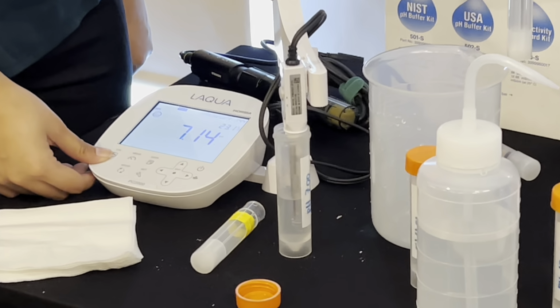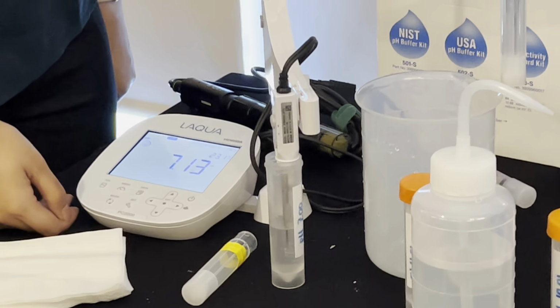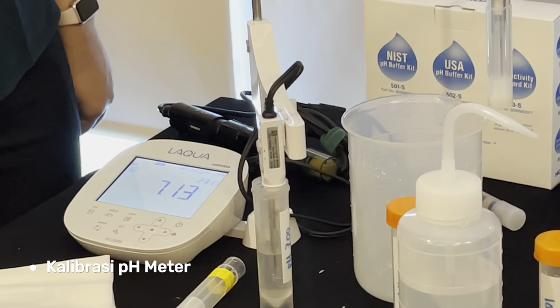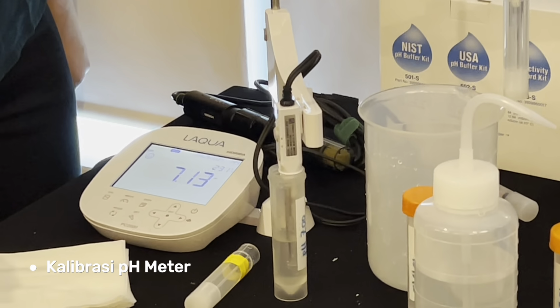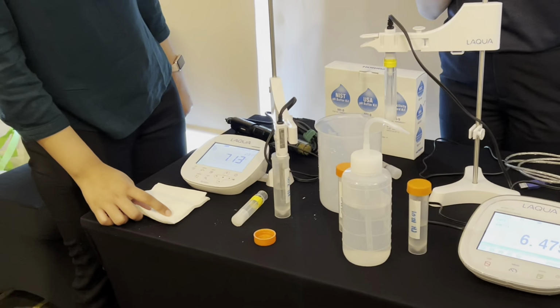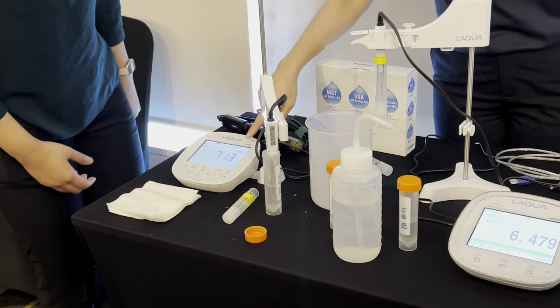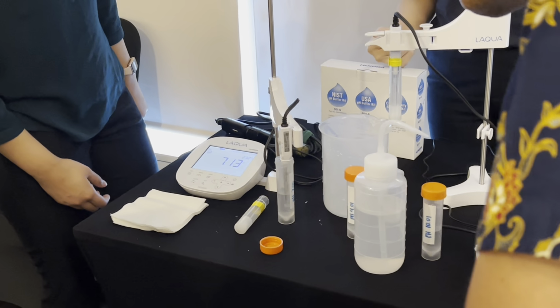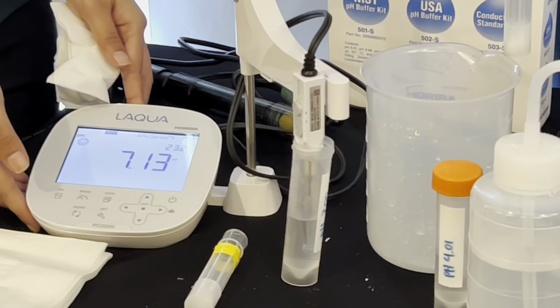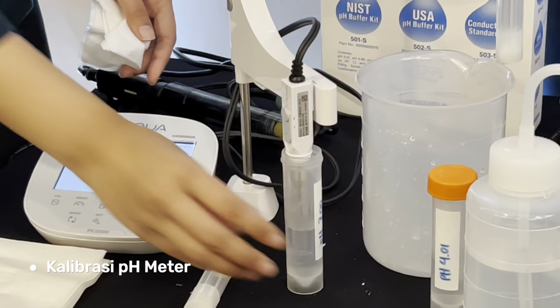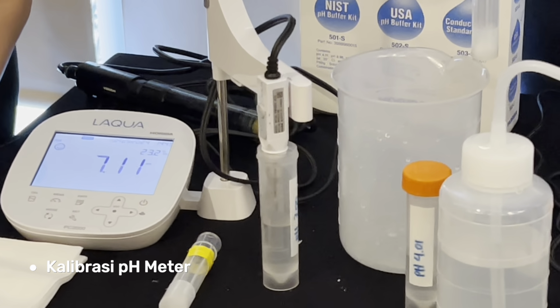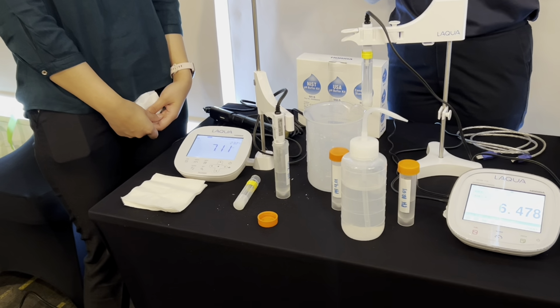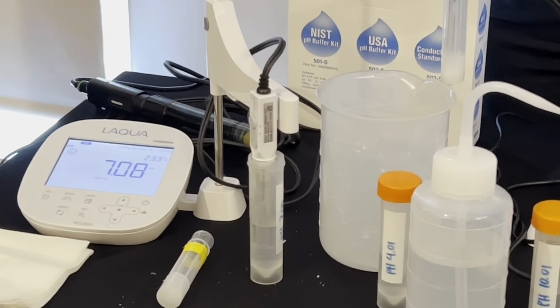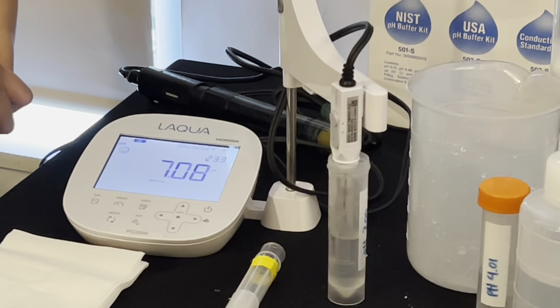Okay, so now, what's our reading? 7.13, right? Without calibration, see? The reading is at 7.13, the temperature is 23.2, right? But this is pH 7 buffer, right? So now we have to do calibration to teach the meter, and now the temperature is 23.3.